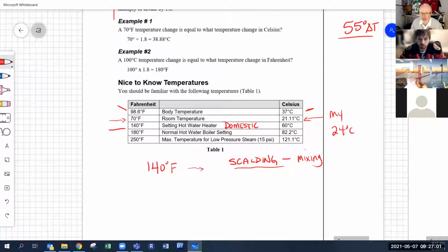The 140 degrees Fahrenheit, if that temperature is maintained, then everything is fine. But as soon as you go below 140, say 120 degrees Fahrenheit, and you had that water sitting for a long time, you can create bacteria in there.